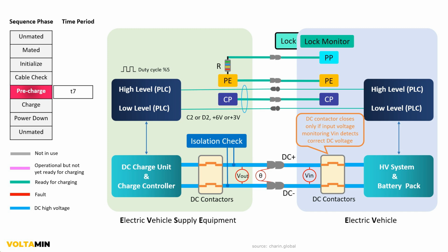During this phase, the DC plus and DC minus lines are shown in blue on both the EVSE and EV sides, indicating the presence of high voltage without active current flow. Communication between the EV and EVSE remains active through the control pilot, CP, and proximity pilot, PP lines, which are depicted in green. These lines ensure continuous monitoring of system parameters, while the isolation check and lock monitor verify the system's integrity and secure connection. Meanwhile, the EVSE gradually adjusts its output voltage, VOUT, to precisely match the EV's battery voltage, VIN, ensuring a safe and smooth transition to the next phase, where full energy transfer begins.